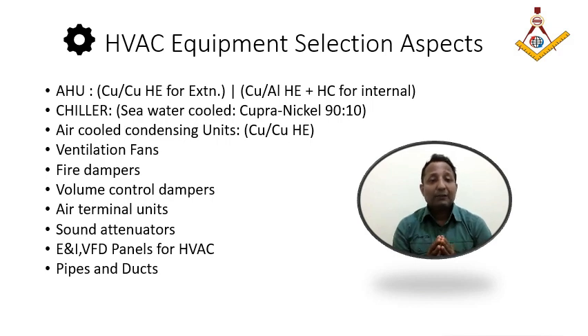So it is always advised to have the AHU inside an enclosed space. If the AHU or any fan is kept outside, as per standards like Shell DEP, irrespective of whether the hazardous area is there or not, it has to be certified for Zone 1. This is a very critical aspect as far as costing is concerned. So it's better to have an enclosed room and keep it inside, on the safer side.